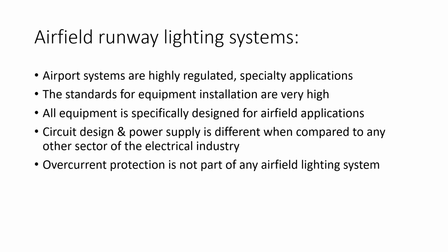Airfield runway lighting systems are highly regulated specialty applications. The standards for the equipment installation are very high. All equipment is specifically designed for airfield applications. The circuit design and power supply is different when compared to any other sector of the electrical industry, and overcurrent protection is not part of any airfield lighting system.